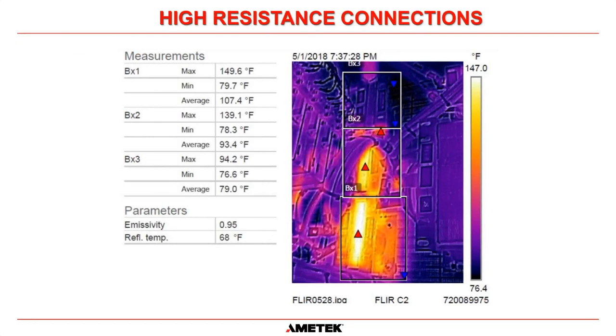And on the complete flip side of that, here's another great example of thermal imaging showing us issues. And this time it's actually the opposite. This was on a huge, I think it was over 100 kVA UPS system. And we have three chokes here. This one here, this one here. They're all identical chokes, one for each phase of the output of the inverter. And because this was such a large system, it had interconnections between two different cabinets. And when the cabinet was assembled on site, one of the connections wasn't made correctly. And this choke here was bypassed.